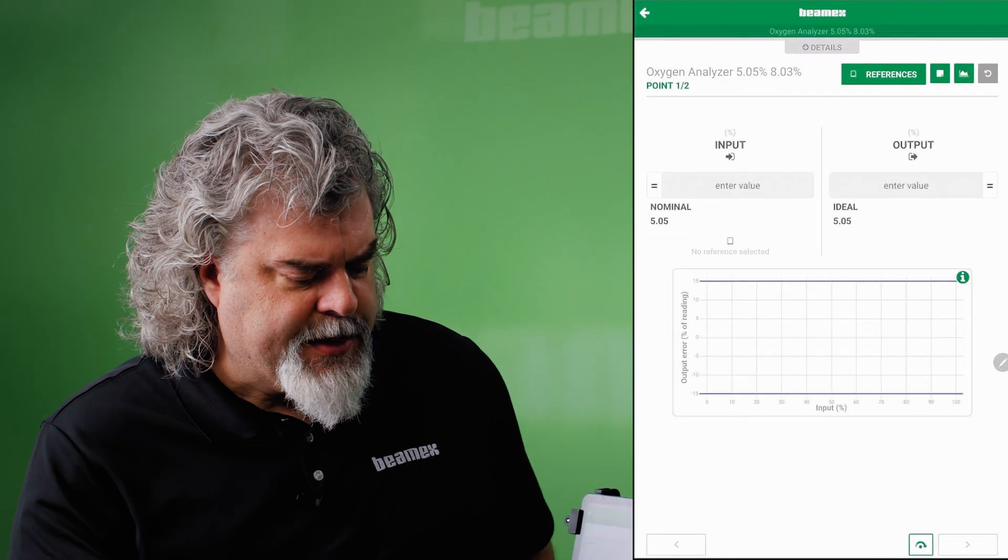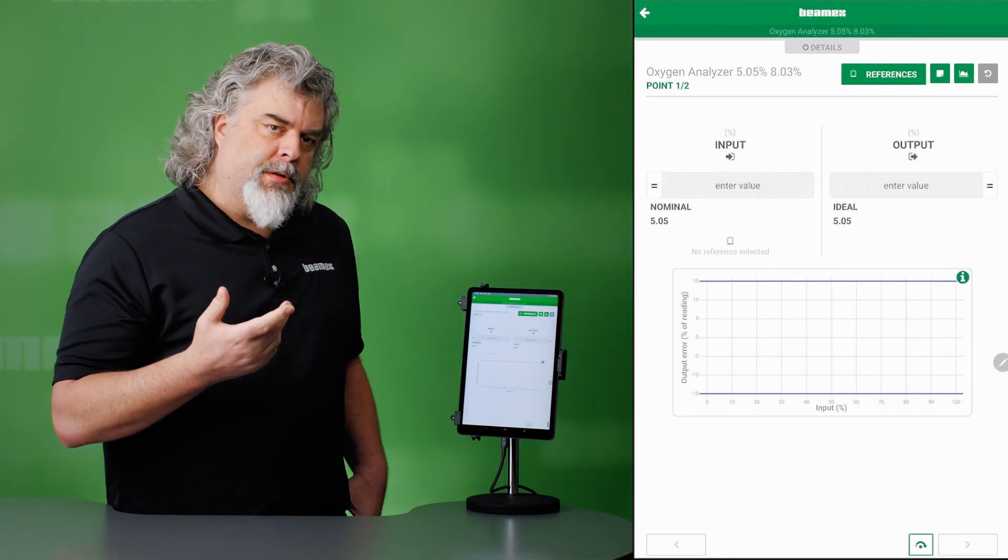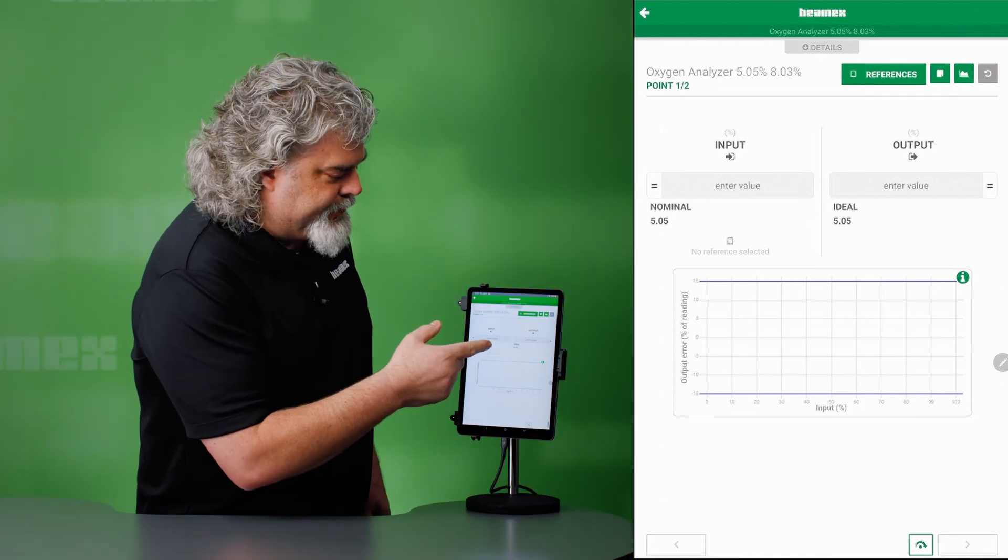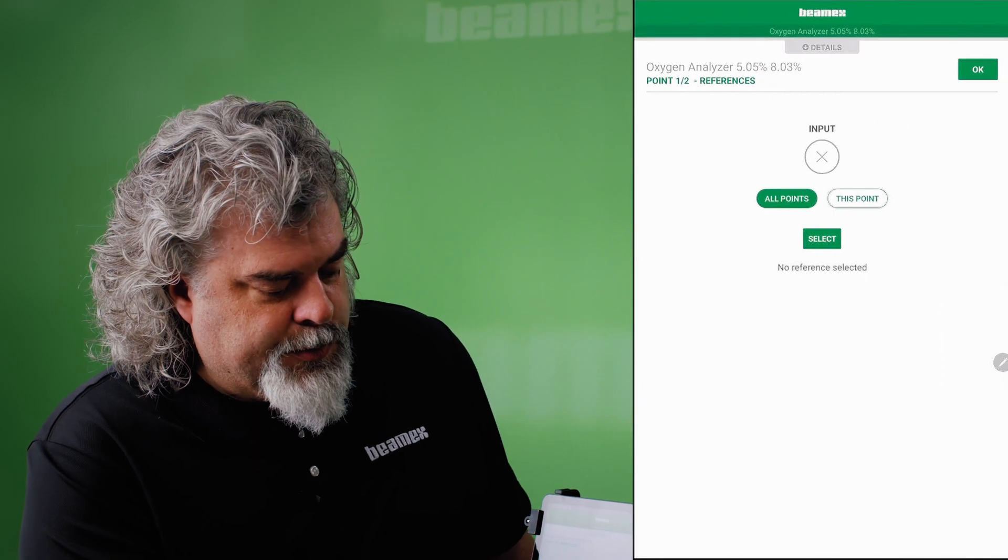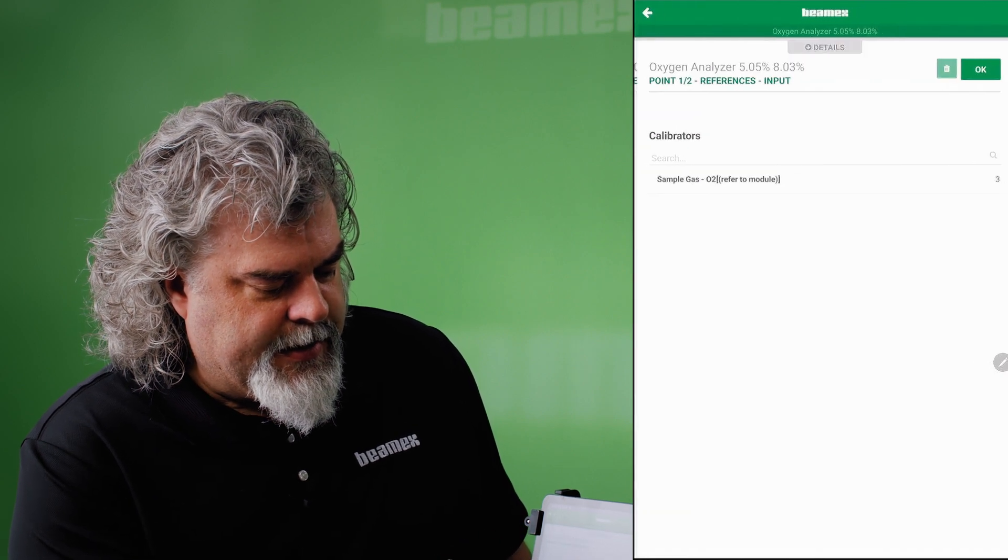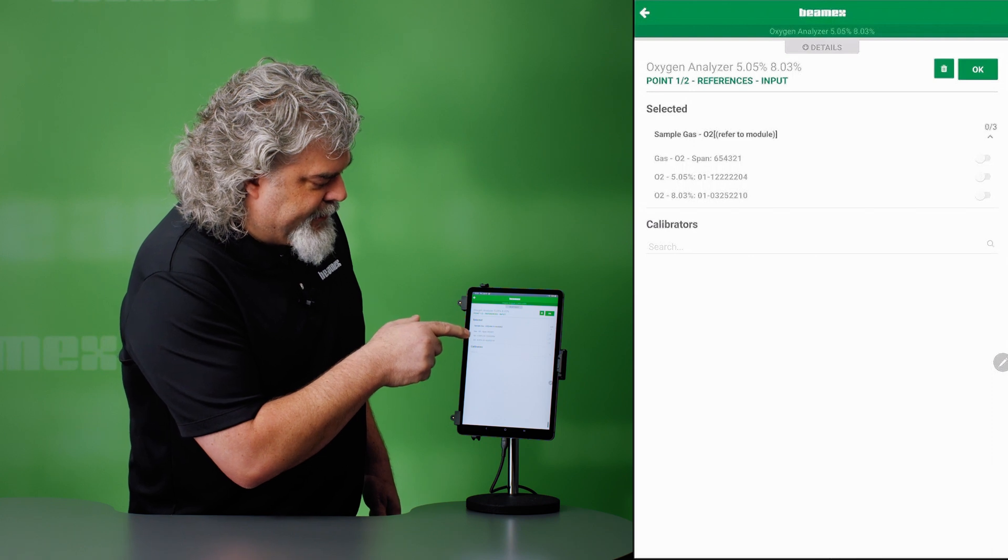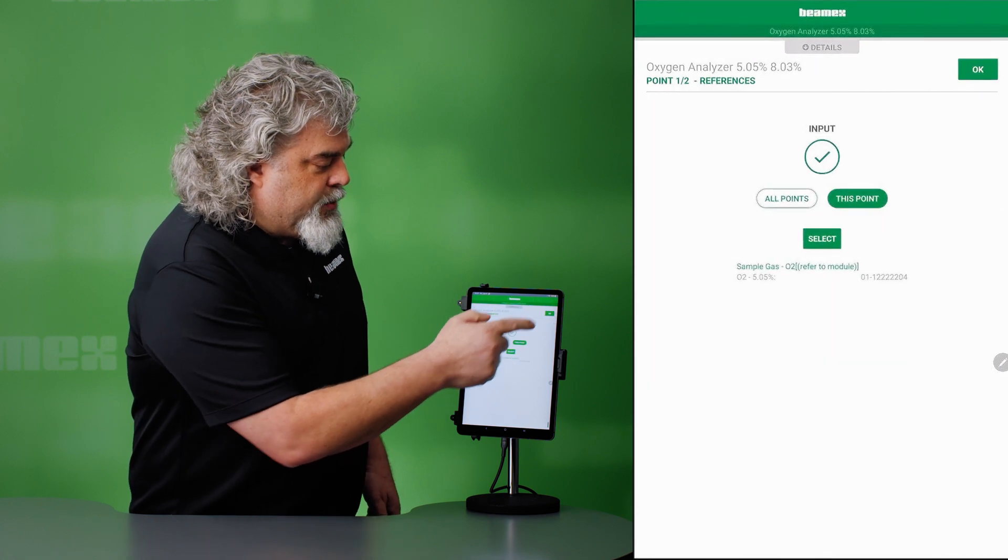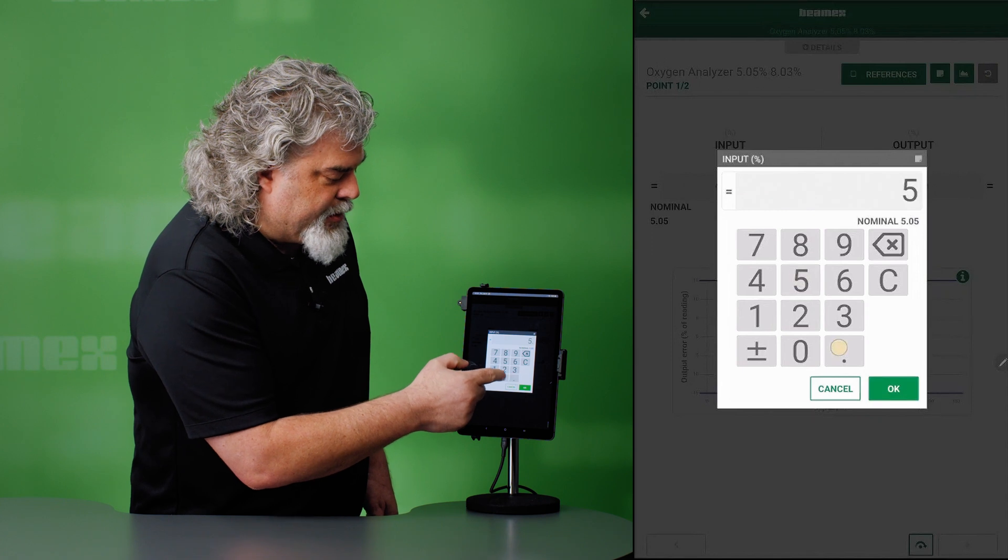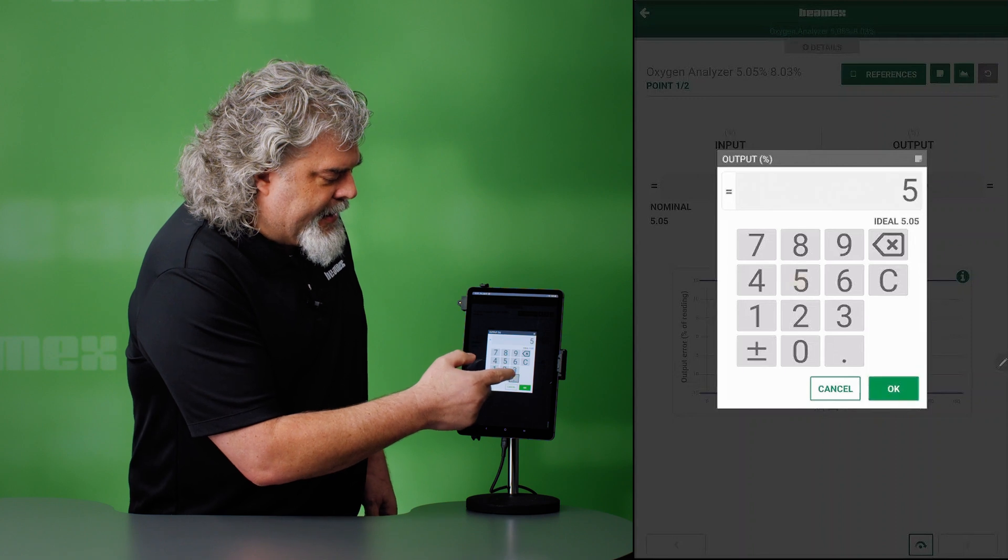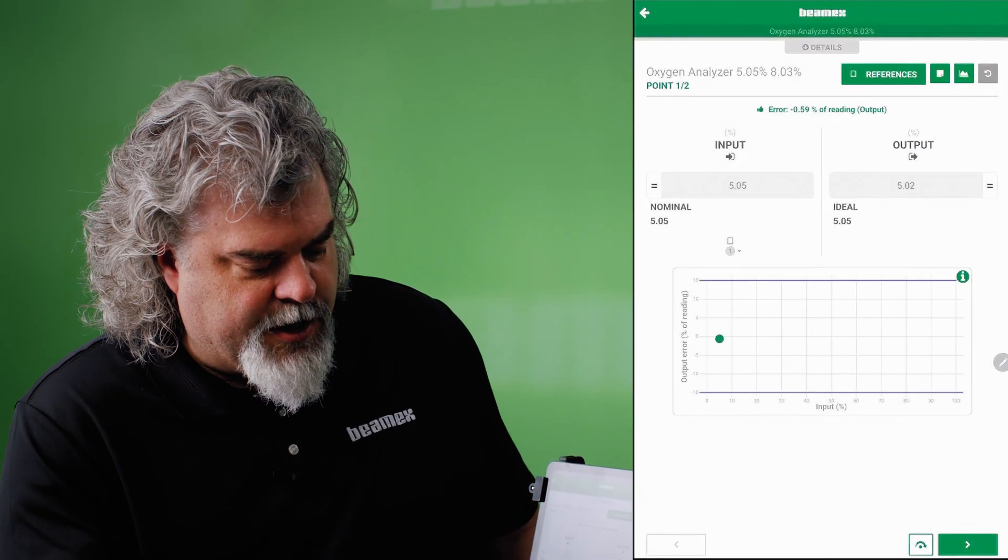So this is a two-point test. We have a gas that's calibrated to 5.05%. And then we'll measure what that indication is on the output. Oh, you know what? I need my reference. So reference on the first point. Not all points. I want a reference for this point specifically. And it's in my sample gases. And it's literally this guy, the 5.05% standard. Hit OK. And once I have that, now I can put in my data. So my gas is 5.05. I already know that. So let me put that in here. And we'll see that the display itself is showing 5.02. So there's a little bit of a deviation.